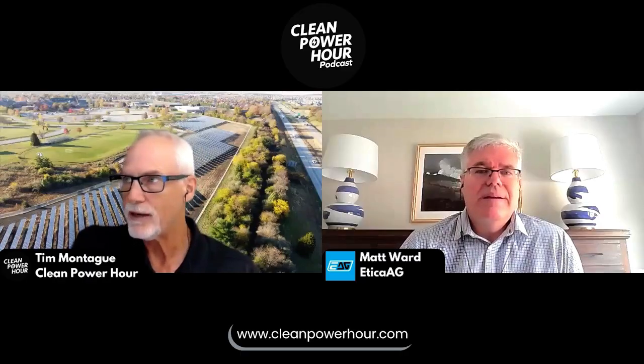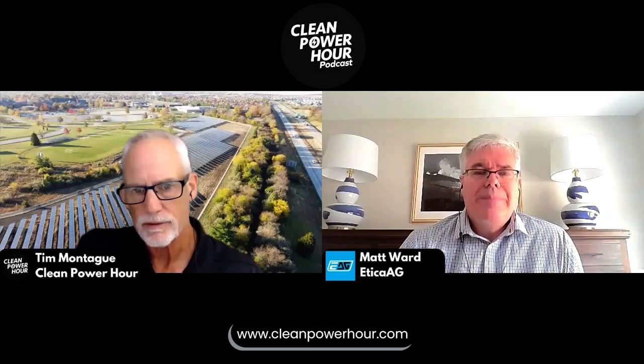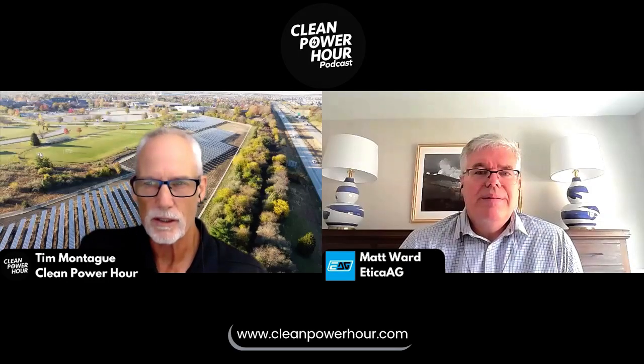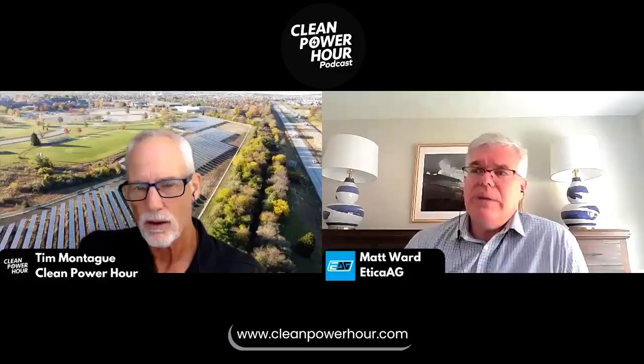Liquid cooling of battery systems is not unheard of, but this is a little different than what others are doing. It is right. Liquid cooling is more about having cooling plates touching the side of the battery cell and running a coolant through that plate for heat transfer. Immersion cooling, on the other hand, actually submerges the entire battery cell, wrapping the liquid all around it on all sides to do that heat transfer and cooling. So it's really a dramatic difference.